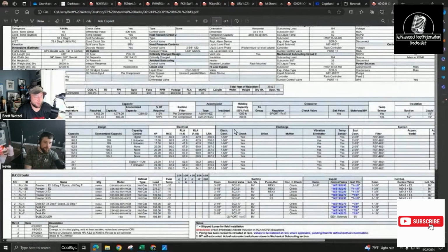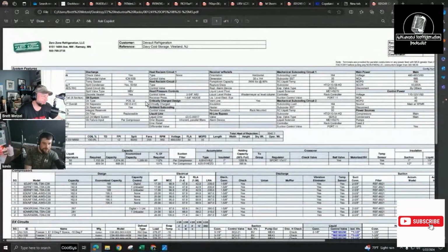Those prints are always wrong, so you add 400 to 700 pounds to it. Wait, no, because I saw an 80% pump out. Oh yeah, here we go, pump down capacity 2600, 2696. So it's probably got about 2,800 pounds of gas in it.